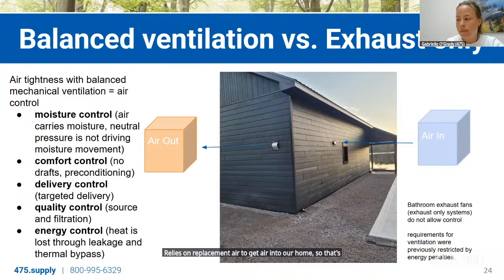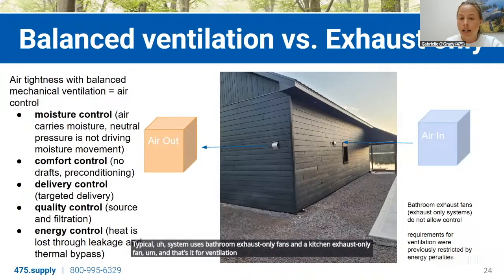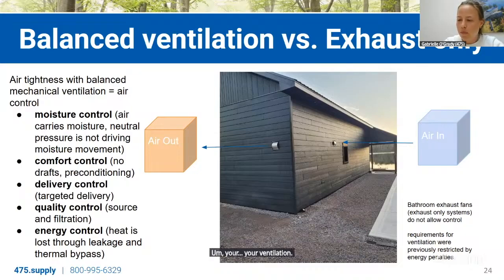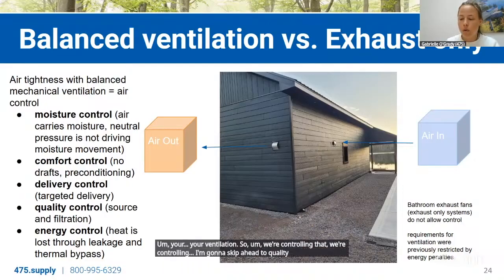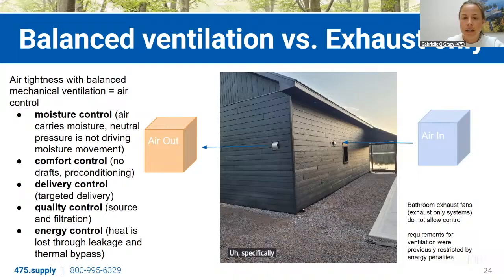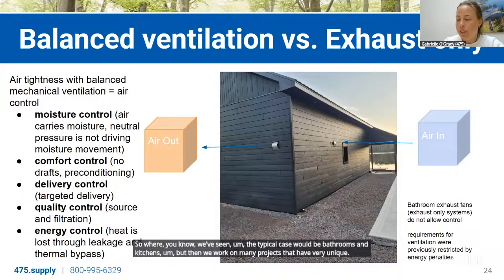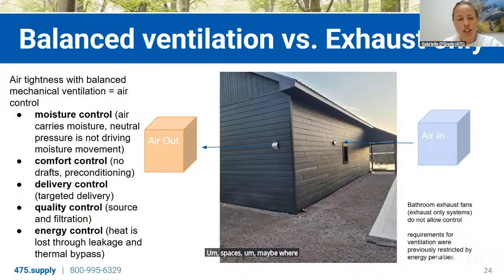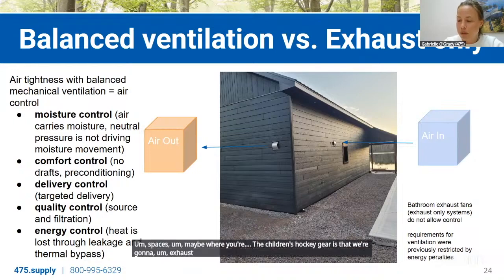So a typical system uses bathroom exhaust-only fans and a kitchen exhaust-only fan, and that's it for ventilation in a lot of homes. That's all that you have, and then the replacement air is your ventilation. So we're controlling that. I'm going to skip ahead to quality because, of course, that replacement air isn't coming from your crawl space or your attic. It's going to be coming from an intentional route and filtered again. And then delivery control. So we can specifically place however much air we need into bedrooms and other living spaces and pull air from contamination sources. So we've seen the typical case would be bathrooms and kitchens, but then we work on many projects that have very unique spaces, maybe where the children's hockey gear is, that we're going to exhaust air from those spaces as well.